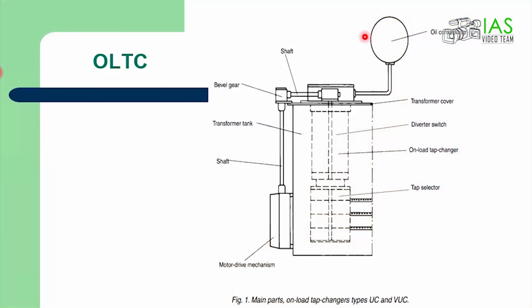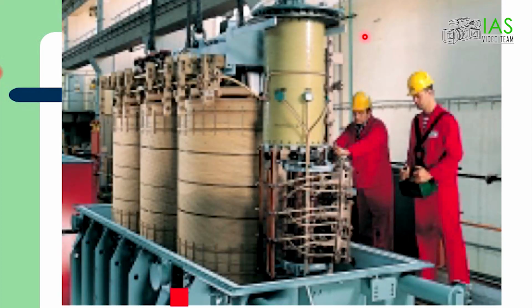And OLTC. So OLTC is the on-load tap changer. The main parts of the on-load tap changer are the gear, inside the transformer tank, and the motor mechanism. The diverter switch is on top and the tap selector is on the bottom. Right? We'll go back to one of those. Yeah, this one. The bottom part is the tap selector, this is the diverter switch.